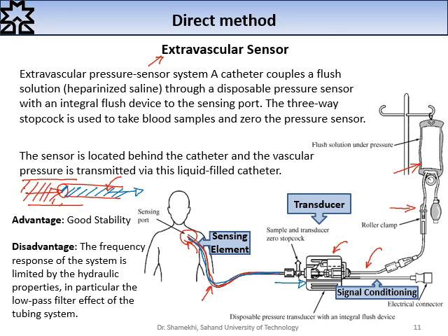The advantage of the system is its stability, and because of the frequency response of the system, we have some limitation in detecting, especially higher frequencies, because some hydraulic properties of the system, including the liquid-filled catheter, the solution, and also the piping system, the wall of the piping system, will affect the frequency response of the system.